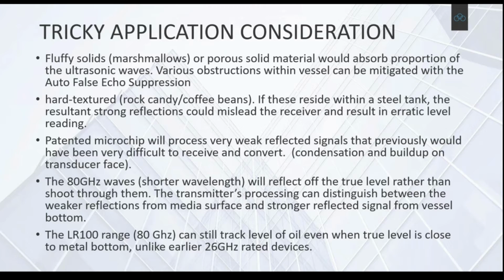Again, when I showed you the narrow beams and the progression of radar from 5 to 26 gigahertz, they had issues where you've got oil, which doesn't have good reflectiveness by its nature. And when the level of oil is, say, half a meter or less, going into 10, 20 centimeters in a big tank, in the past the beam would shoot through and not reflect off the surface of the actual oil, but shoot through and hit the bottom and come back up.